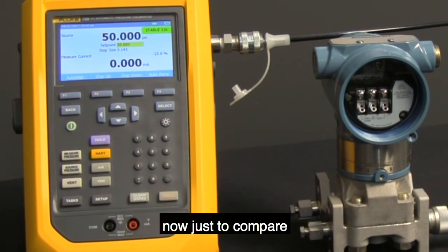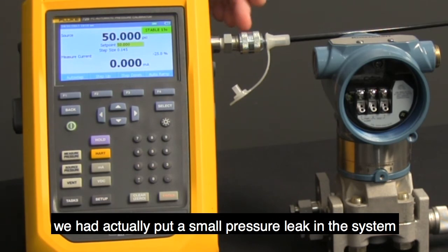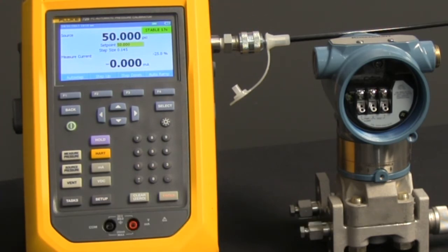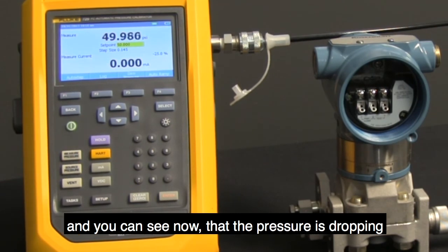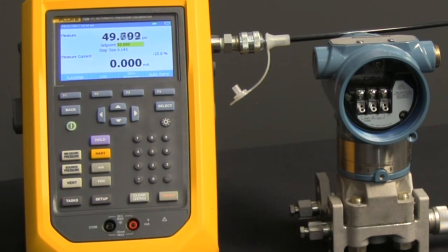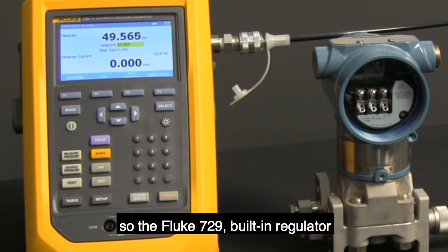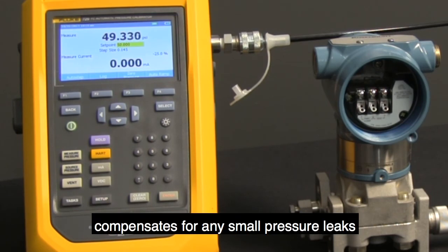Now just to compare, we actually put a small pressure leak in the system. If I set the calibrator to measure, the regulator turns off and you can see now that the pressure is dropping. So the Fluke 729 built-in regulator compensates for any small pressure leaks.